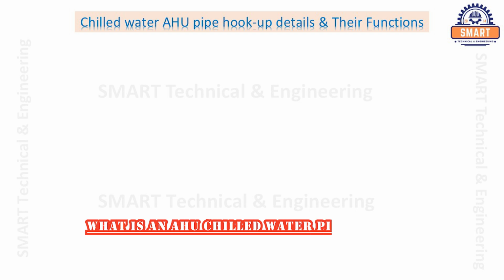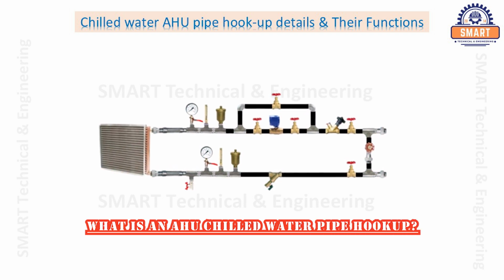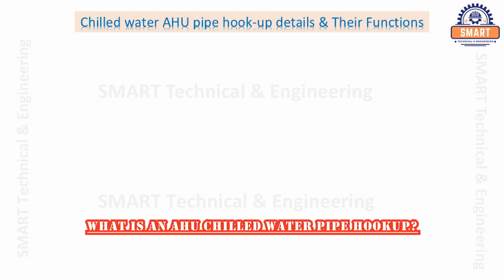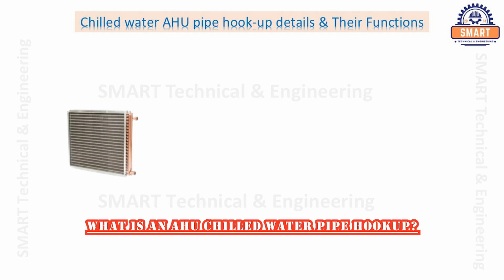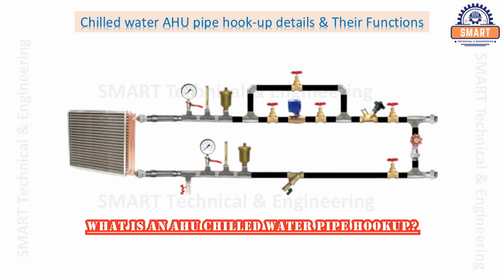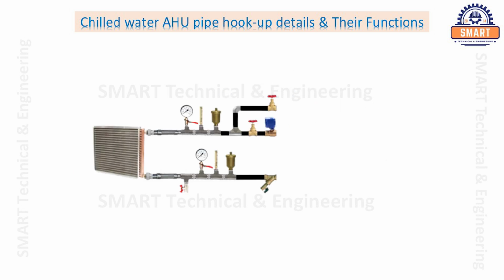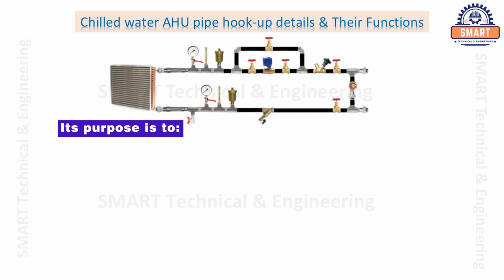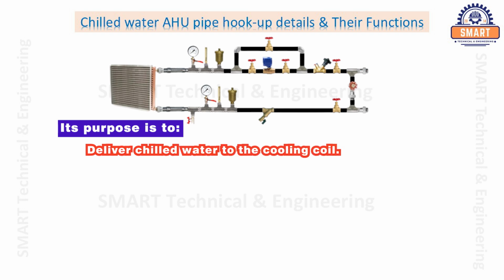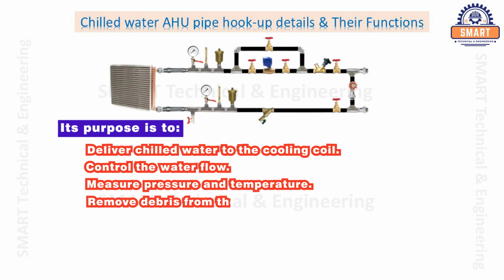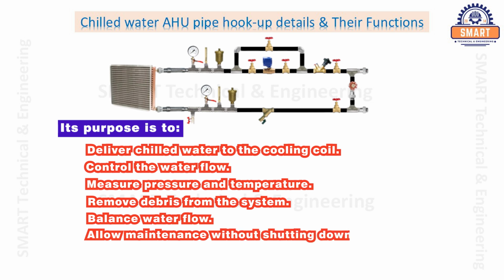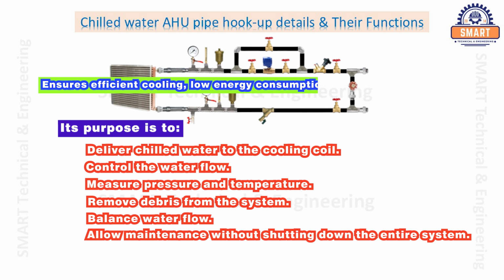What is an AHU chilled water pipe hookup? The chilled water pipe hookup is the piping arrangement that connects an air handling unit cooling coil to the building's chilled water distribution system. Its purpose is to deliver chilled water to the cooling coil, control the water flow, measure pressure and temperature, remove debris from the system, balance water flow, and allow maintenance without shutting down the entire system. A properly designed pipe hookup ensures efficient cooling, low energy consumption, and reliable operation.